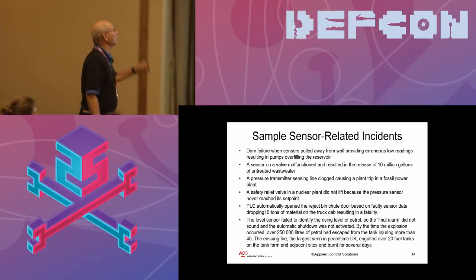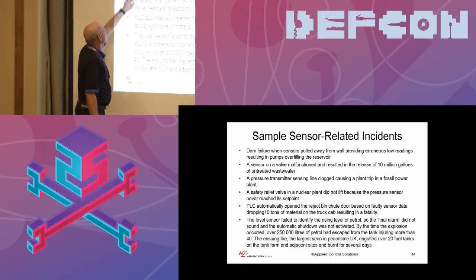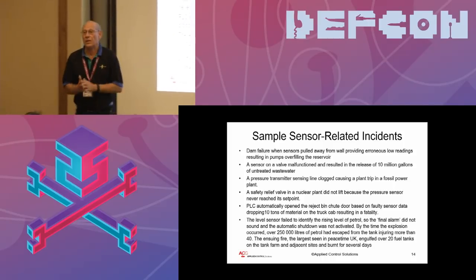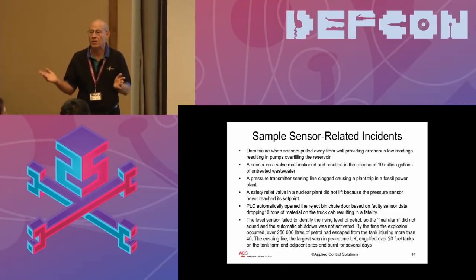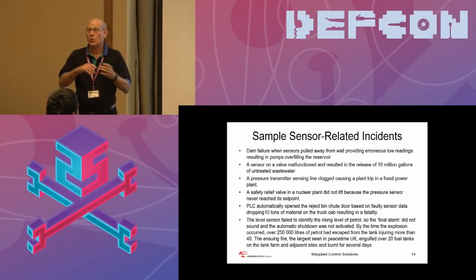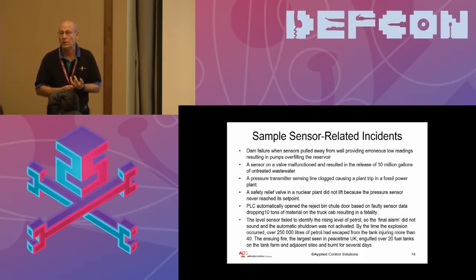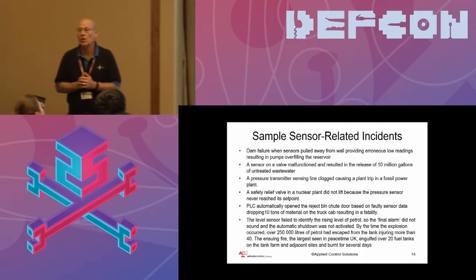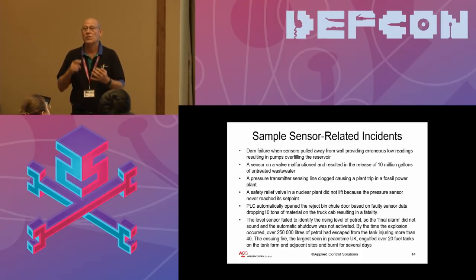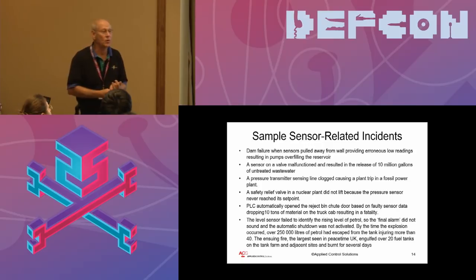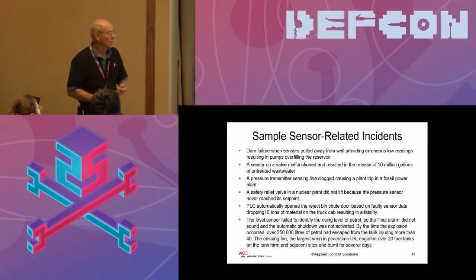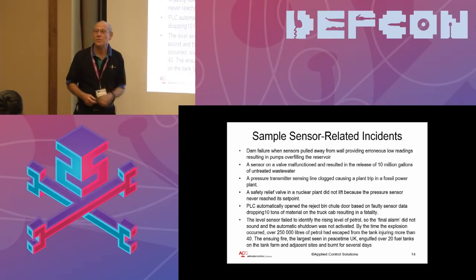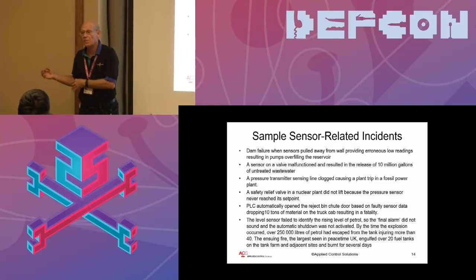Here are real things. And 2 weeks ago, I was at a power plant. It had tripped - they had tripped it, in other words, shut it down. Very large plant. A pressure sensor reached a set point. Why? A sensing line clogged. It is impossible to see that from network monitoring. But if you're looking at the process, it becomes very obvious something is going on with that sensor.